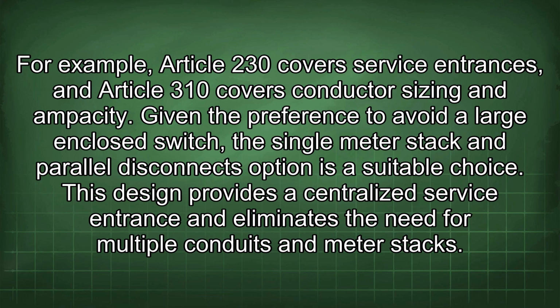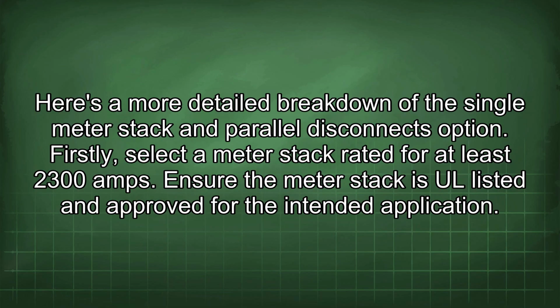Given the preference to avoid a large enclosed switch, the single meter stack and parallel disconnects option is a suitable choice. This design provides a centralized service entrance and eliminates the need for multiple conduits and meter stacks. Here's a more detailed breakdown of the single meter stack and parallel disconnects option. Firstly, select a meter stack rated for at least 2300 amps. Ensure the meter stack is UL listed and approved for the intended application.